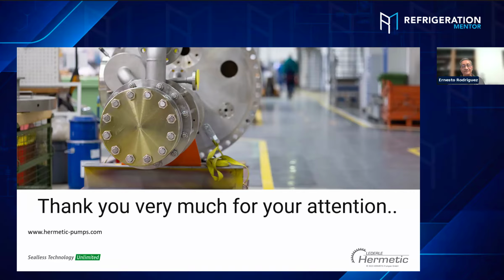I have seen major petrochemical companies, or companies with experience, whose packages come from Europe, but they install VFDs. I say that is a problem. For example, one company tried to use the VFD to control the level of the vessel. If the level increases, they reduce the speed of the pump. If the level starts demanding too much liquid, they increase the speed of the pump, and they replace pumps like crazy. I say this is not the way to do that. You need some type of level control, but controlling the level of the vessel by controlling the flow of the pump is a big mistake, most of all for CO2. We did it before with water or oil, but you're not pumping water, you're not pumping oil, you're pumping a thermodynamic fluid. That is the big problem.